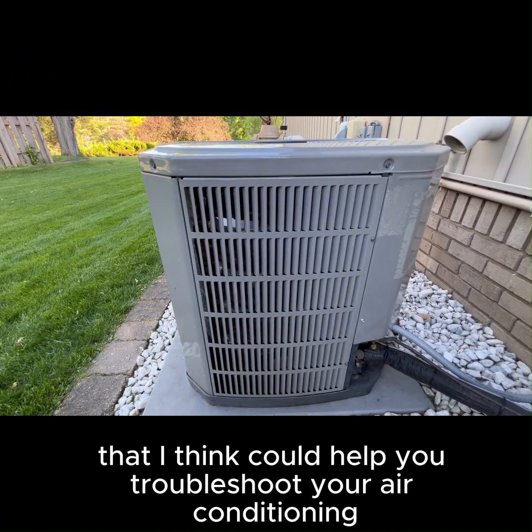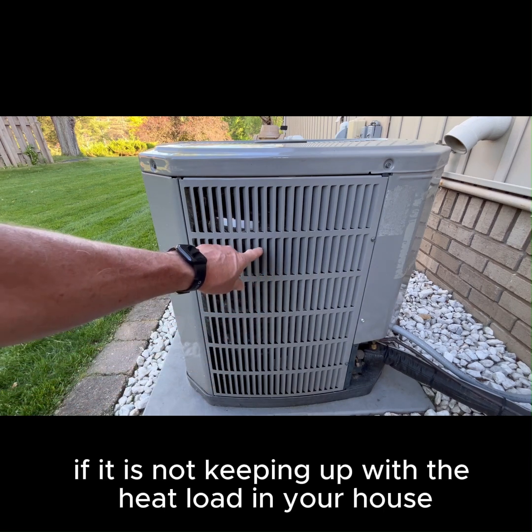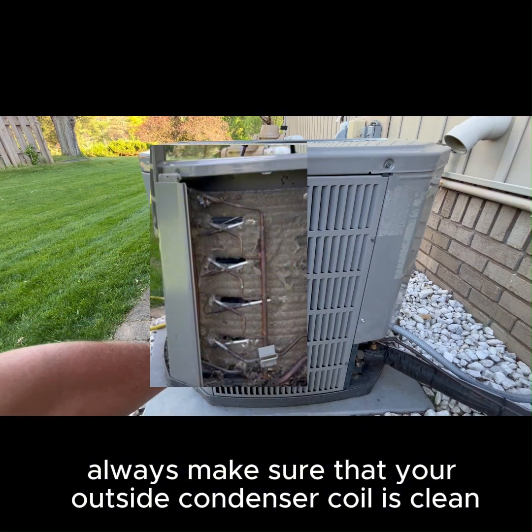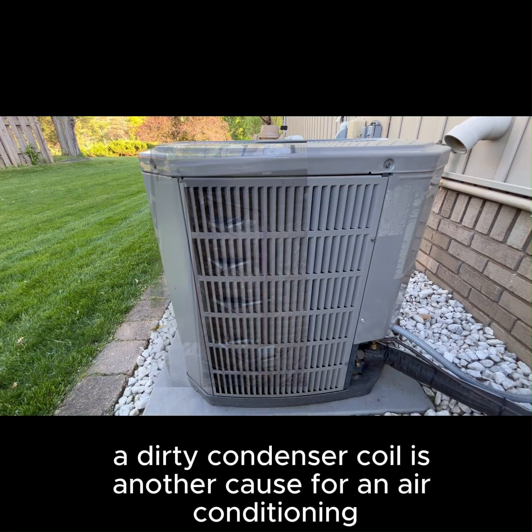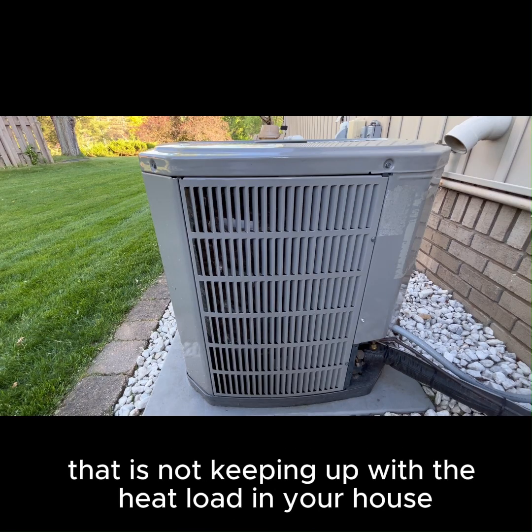One more thing that I think could help you troubleshoot your air conditioning if it is not keeping up with the heat load in your house: always make sure that your outside condenser coil is clean. A dirty condenser coil is another cause for an air conditioning that is not keeping up with the heat load in your house.